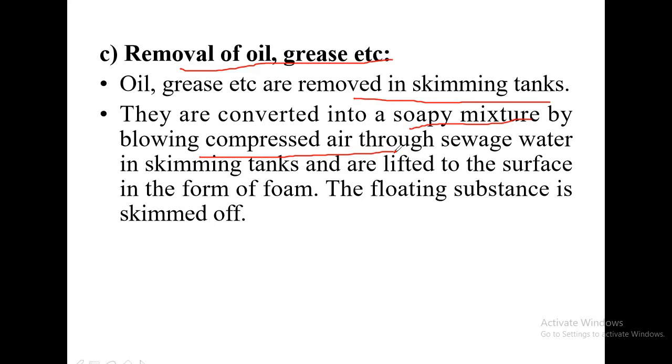Because of the action of soap, oil, grease, water and compressed air, froth or foam is formed. This foam or froth is lifted to the surface and carries along with it oil and grease. From the top the froth and foam is skimmed off. This is how you can separate oil and grease.